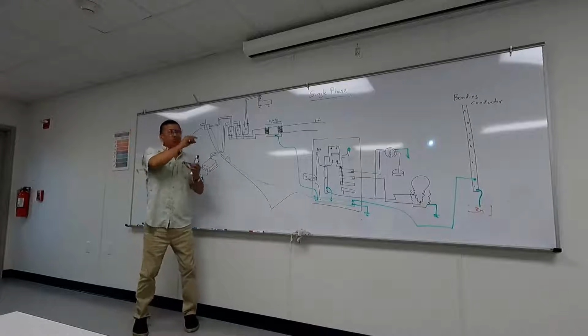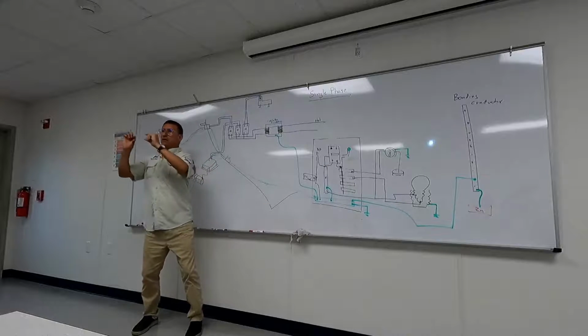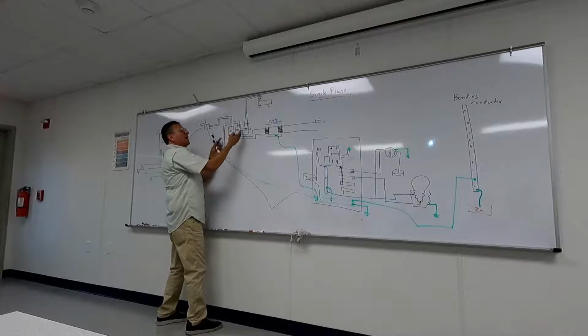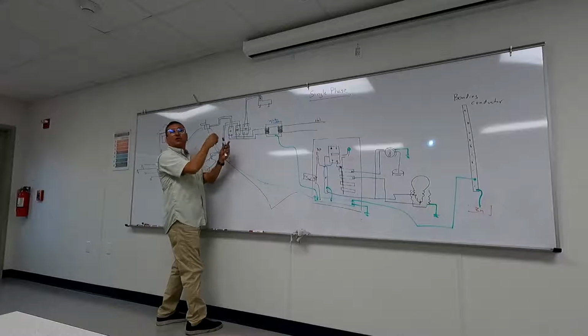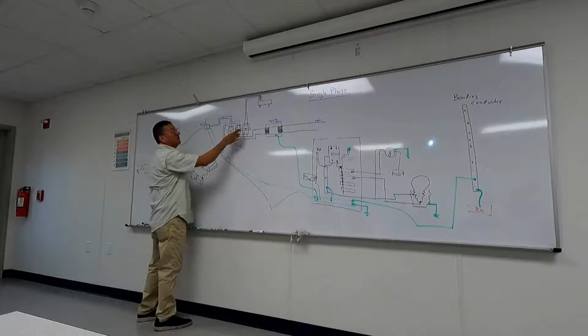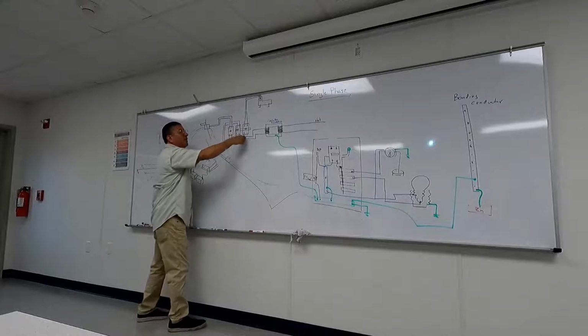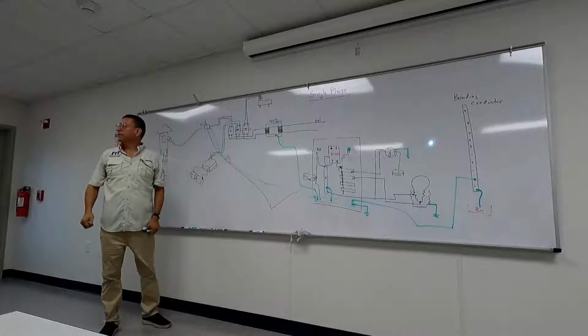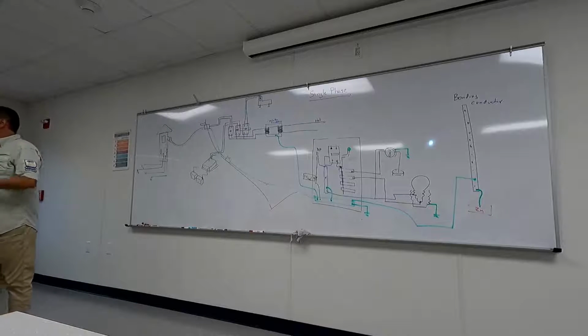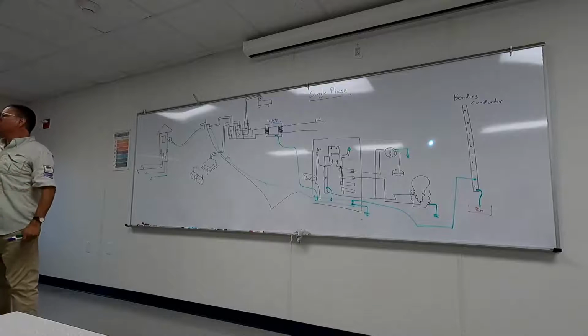You remember in those you have a slide bar, a metallic bar, and you move the bar and you block the other two breakers. That's too simple. At this moment, this and this are blocked. You only have access to this. Ready? Let's say theoretically you were to turn on two at the same time. It's not possible because the bar only allows you to turn on one breaker.